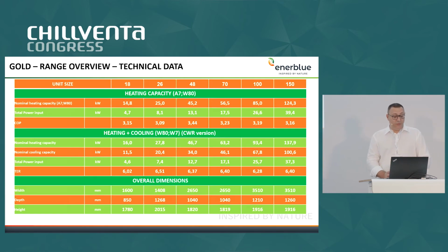To give you an overview about the technical data, these are our sizes, so from 18 up to 150. And you can see, working with outlet water temperature 80, we have always COP higher than 3. For the heating plus cooling version, the COP or the TER will be always higher than 6. So in terms of energy efficiency, both solutions are very, very good. And dimensions are quite small. We have a small footprint, and this unit could be installed in an easy way, more or less everywhere.